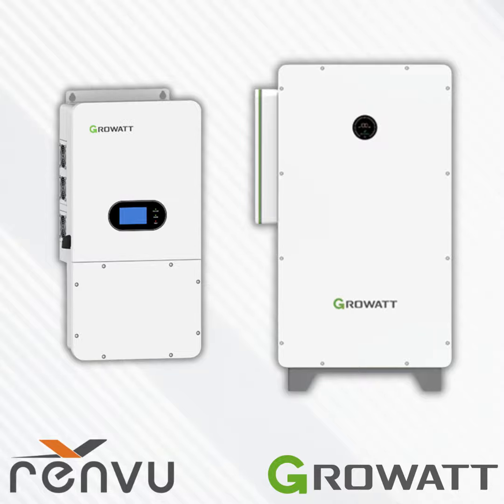So yeah, IP66 ratings on those. They can work on grid and off grid. I'll get into that a little bit more later, but in essence, everything that we saw with the SPH, where it has every component pulled in, the same is true for the WIT. So we really tried to make this one component for everything and reduce all the extra third-party equipment necessary. It's UPS capable, so the transfer time is 16 milliseconds, and you can parallel it 6 sets in on-grid and 3 sets in off-grid mode. So, for example, if you need 300 kilowatts off-grid, we can support that with 3 of the 100 kilowatt WITs.